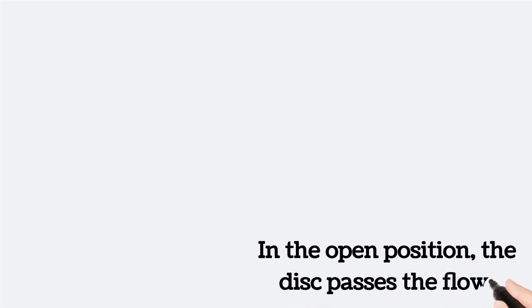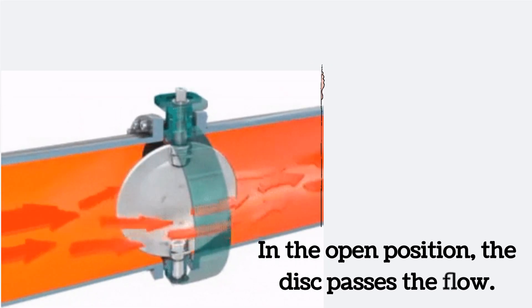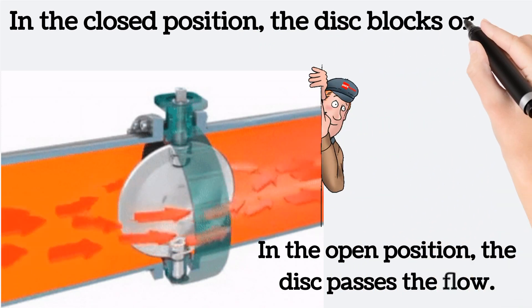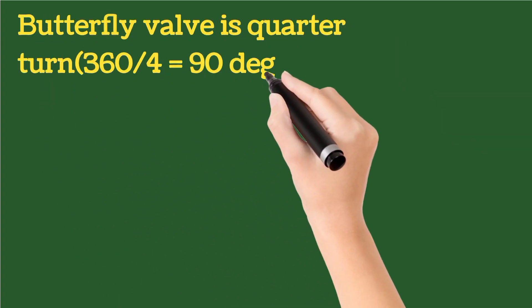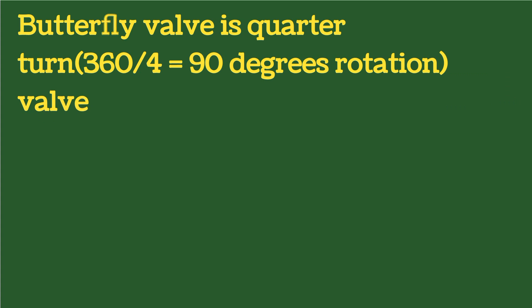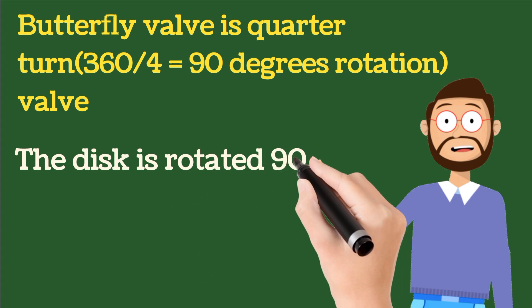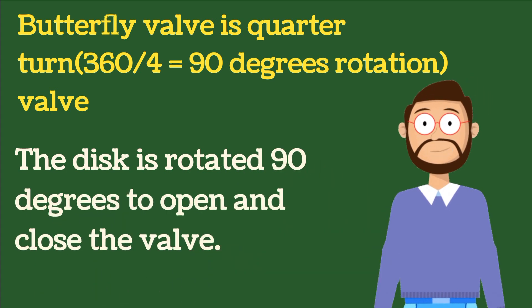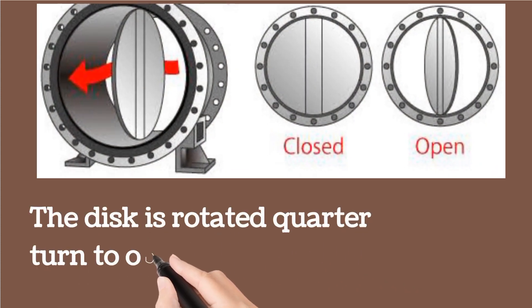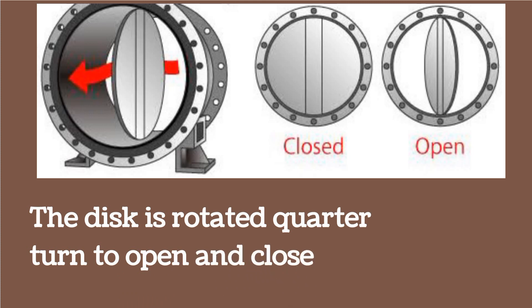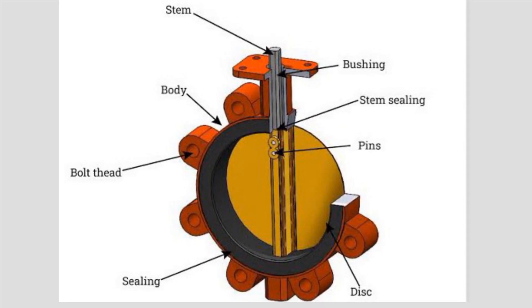When the valve is opened, the disc will pass the flow. When the valve is rotated and closed, the disc will stop the flow. The butterfly valve is also known as a quarter-turn valve — meaning a 90-degree rotational valve (360 degrees divided by 4). The disc is rotated 90 degrees to open and close the valve. In these images, butterfly valves are shown in open and closed position, with the disc clearly rotated 90 degrees or a quarter turn. Some parts of the butterfly valve are also shown.